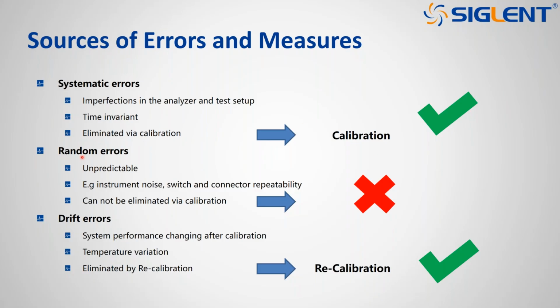This is the first part. There are of course random errors, so they are unpredictable. Just think about if you change the device, so you have multiple devices, they are all filters, all the same filter, and you want to compare these filters against each other. Even opening screws and closing screws might create random errors in this case. And this is something you cannot avoid with calibrating or recalibrating. So we have to live with it, but in general we should roughly know about it.